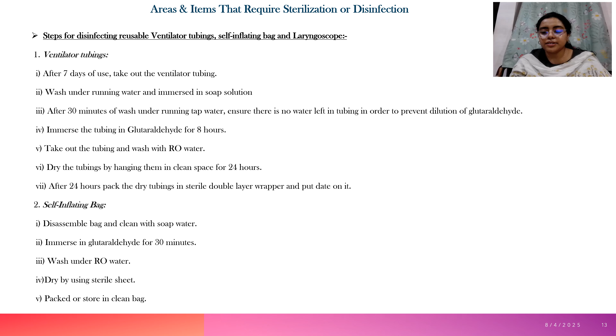So we are disinfecting ventilator tubings after 7 days of use, taking out the ventilator tubings, washing them under running water and immersing them in soap and water solution. And after 30 minutes, we wash under running tap water, ensuring that there is no water residue in the tubing in order to prevent dilution of glutaraldehyde. Once it has been dried properly, we completely immerse the tubing in glutaraldehyde 2% for 8 hours, take out the tubing and wash with RO water. Dry the tubings by hanging them in a clean space for 24 hours. After 24 hours, we pack the dry tubings in a sterile double layer wrapper and put date on it.